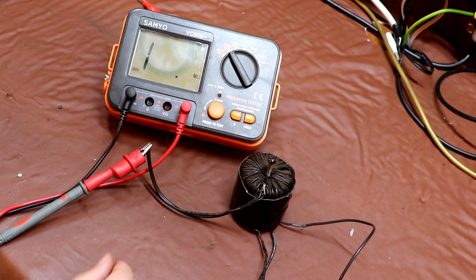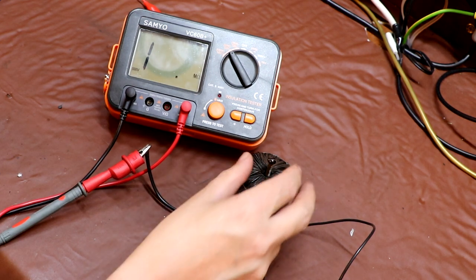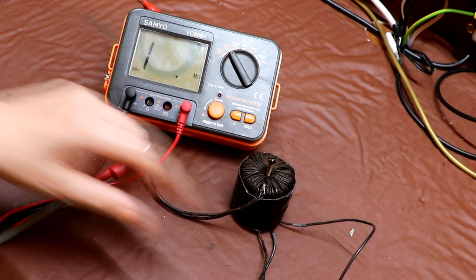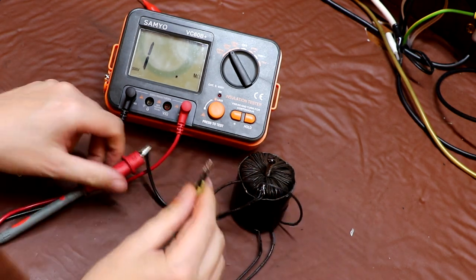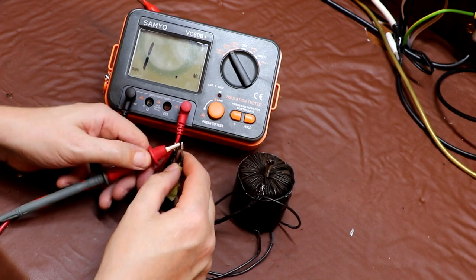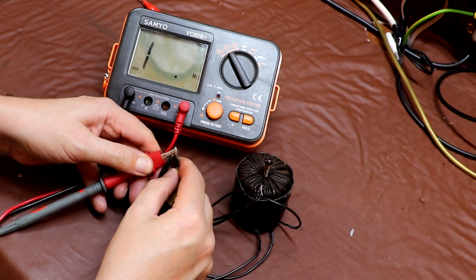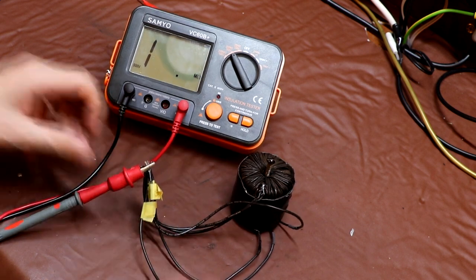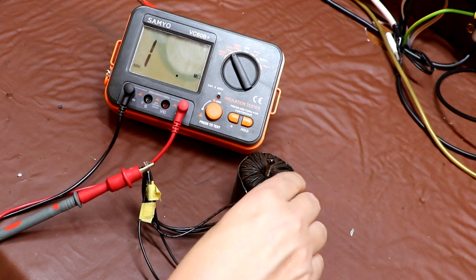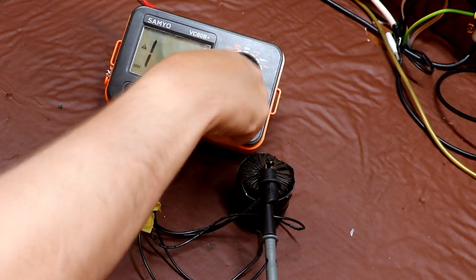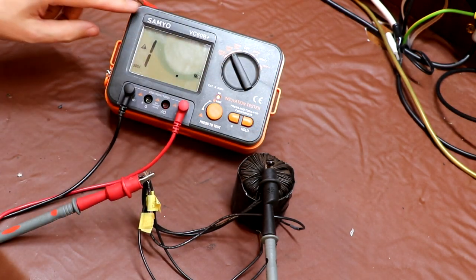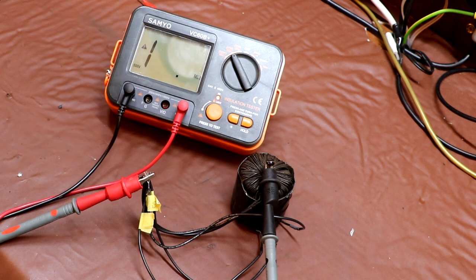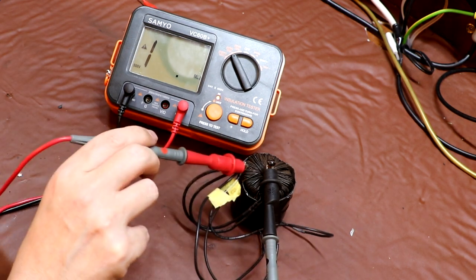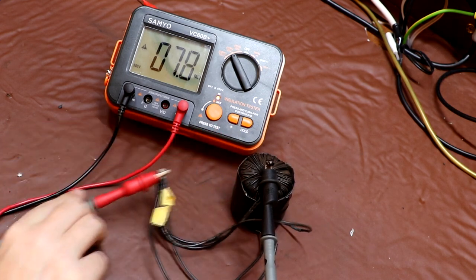Now the other test that you want to do is make sure that there's no short circuit between any of the windings and the core of the transformer. So the way that we do that is we get all the wires and I'm going to short them all together. Hopefully that's got it. And now I'm going to put the clip onto the metal part of the transformer. Let's turn on again. And again, we've got a high reading, in fact it reads infinite on this meter. Again, just always check the meter. Yeah, the meter's reading good.